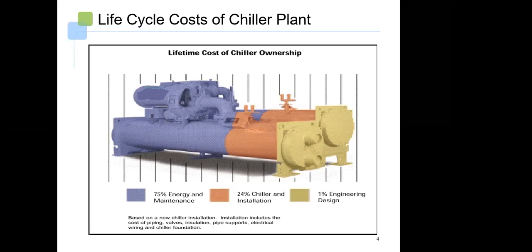And secondly, because these products consume the highest energy, there are government regulations which mandate that the chilled water plant or chiller plant should not consume more than this much energy per ton, which is the effective capacity of the chiller. So they drive certain strategies so that they can push the industry to develop more and more efficient products.